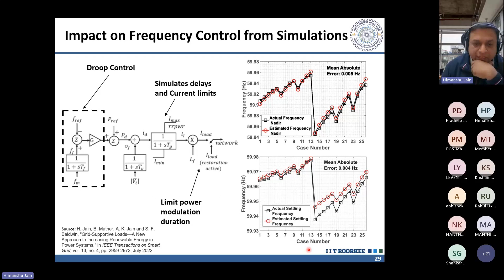If we do provide this capability, we can take the frequency from 59.9 all the way to 59.96 hertz. It looks very small, but it's quite large for a grid of ERCOT scale. So those are the kinds of impacts we could get if we are able to obtain this droop kind of response from our loads. And again, inverter-based loads is what really helps us achieve that.